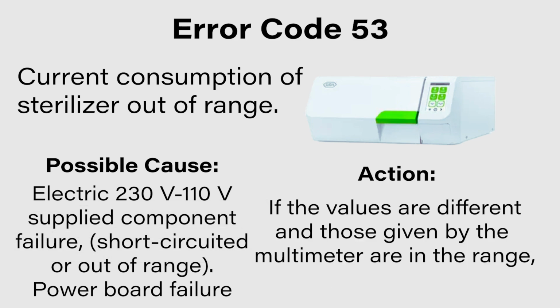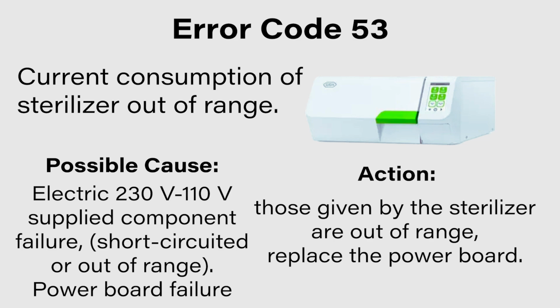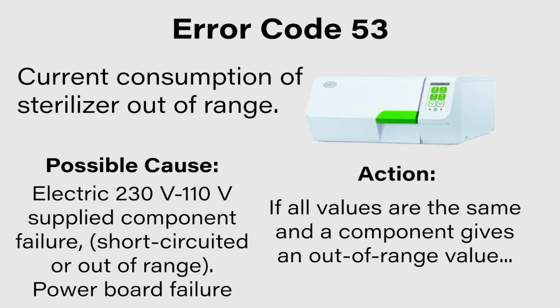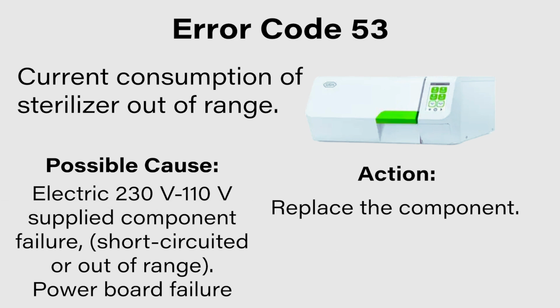If the values are different and those given by the multimeter are in range, while those given by the sterilizer are out of range, replace the power board. If all values are the same and a component gives an out-of-range value, replace the component.